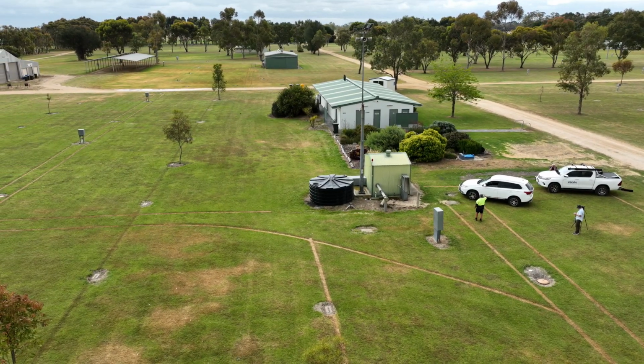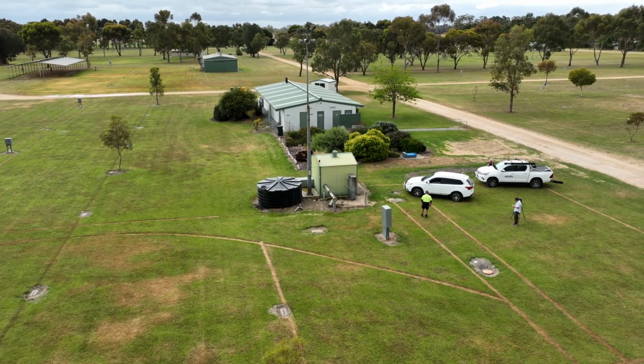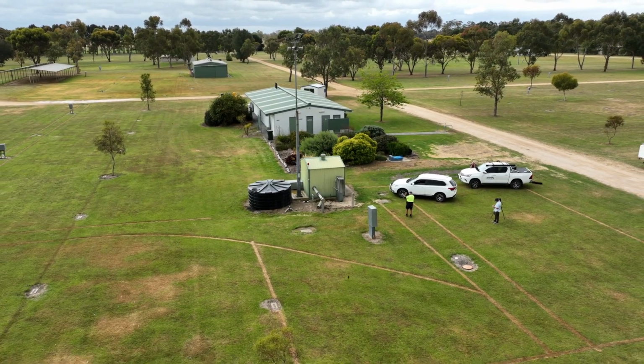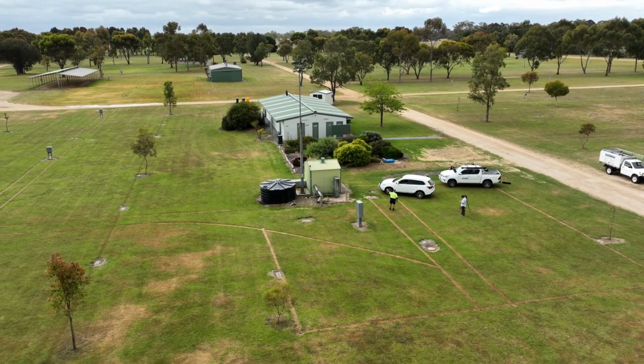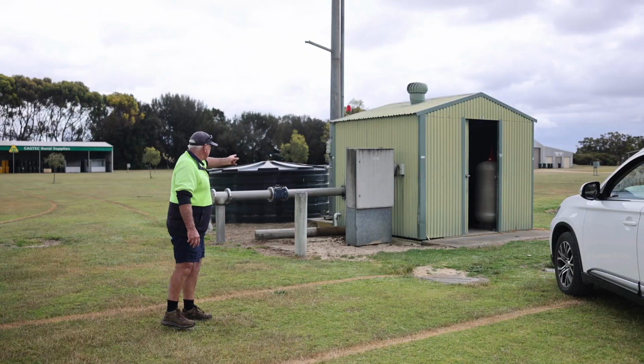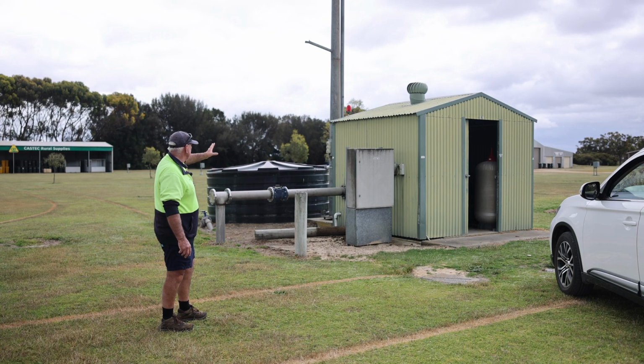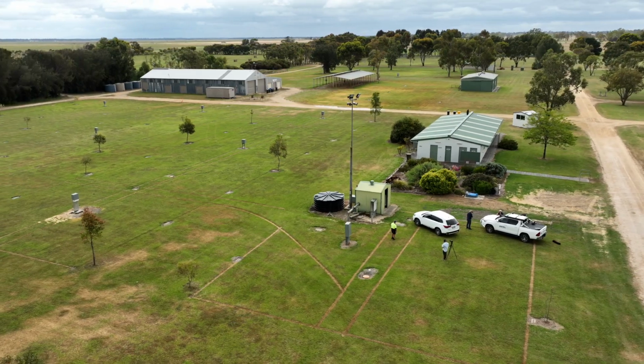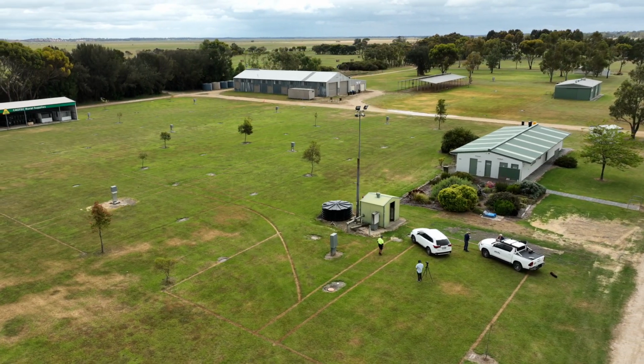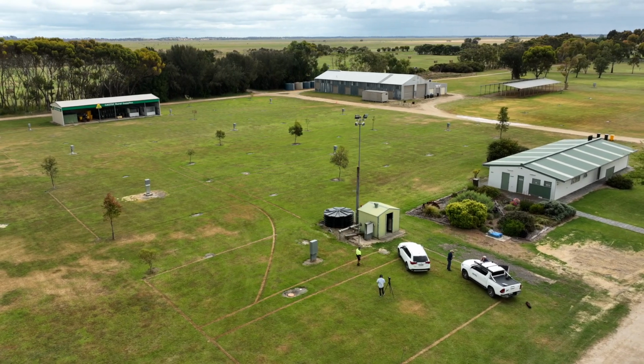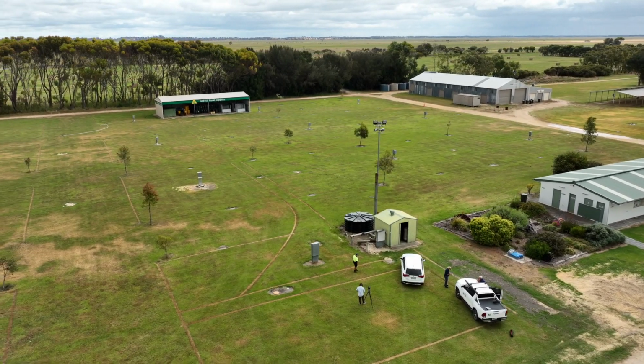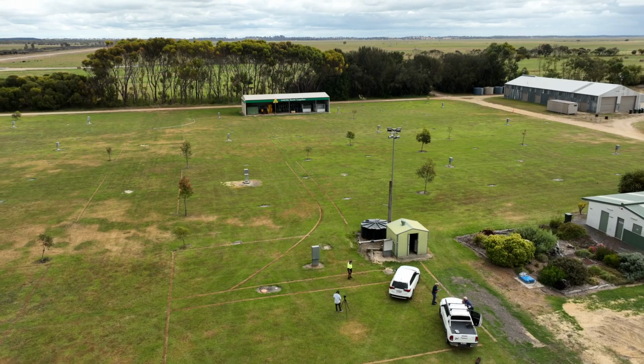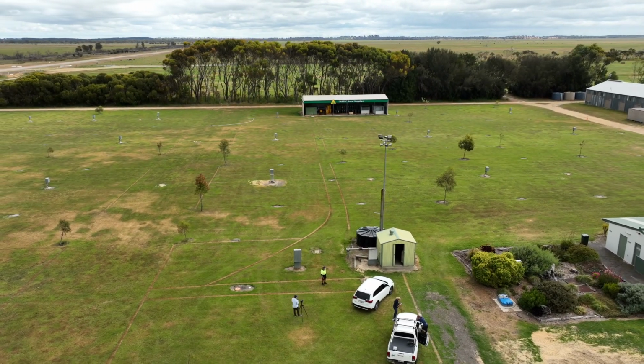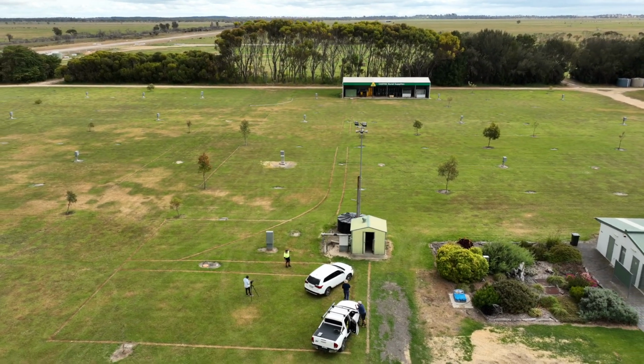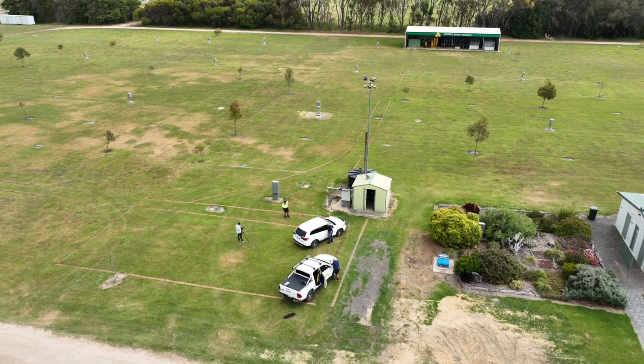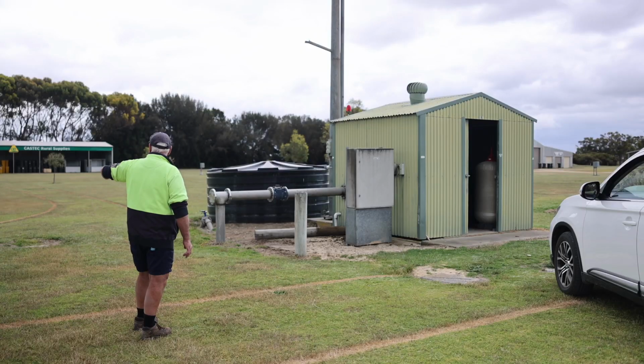So what we did is we pulled out half the circuits from that switchboard and put them into the outgoing ones, into that junction box, which is marked switchboard 36, but it's a junction box. Then we ran those as submains, extended them back into that switchboard in here, which we then ran a submain down to that genset pit, or incoming mains to that genset pit. Put a big genset over there, and it went off to all the rows.